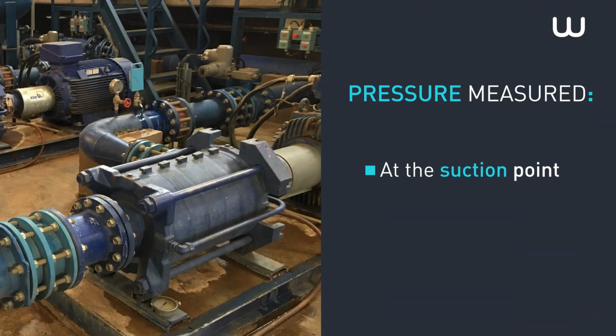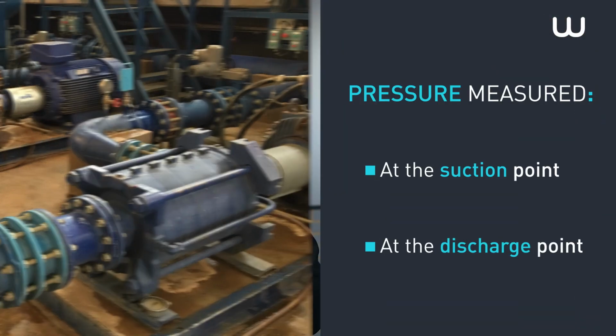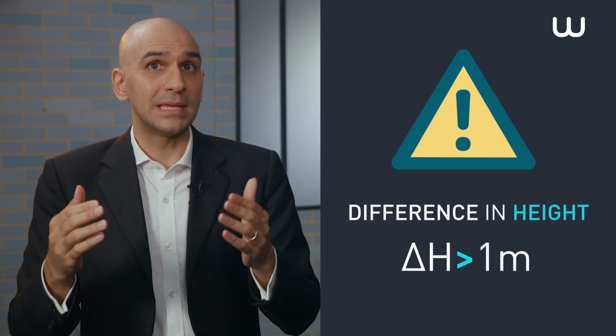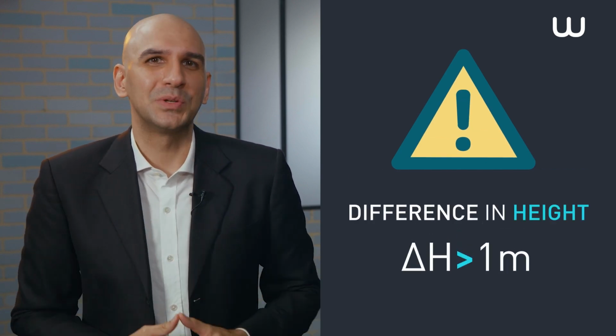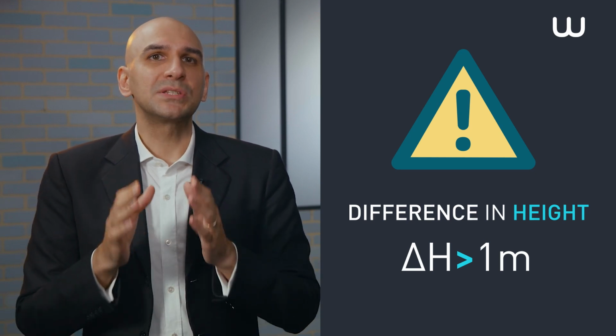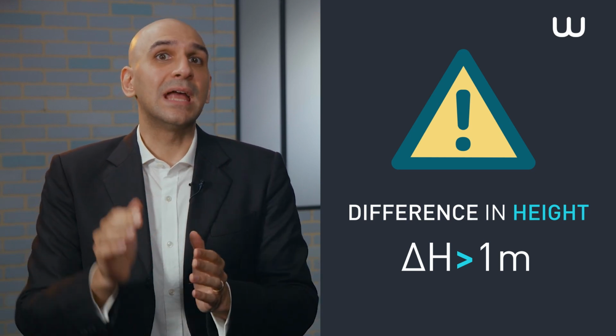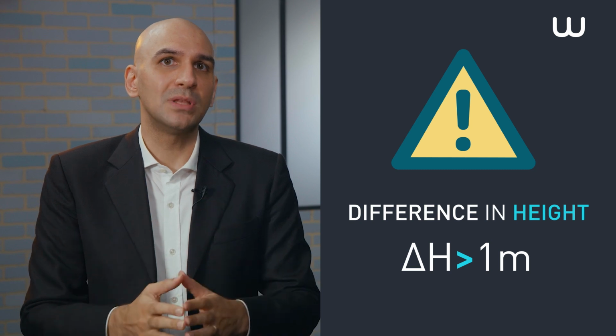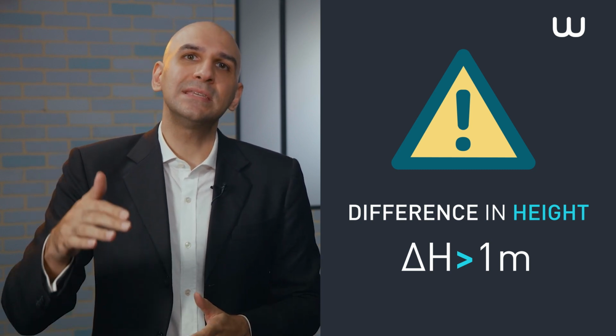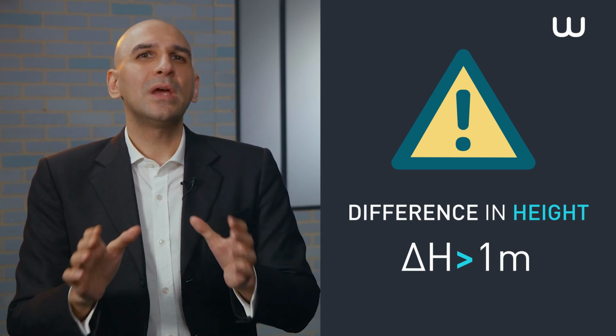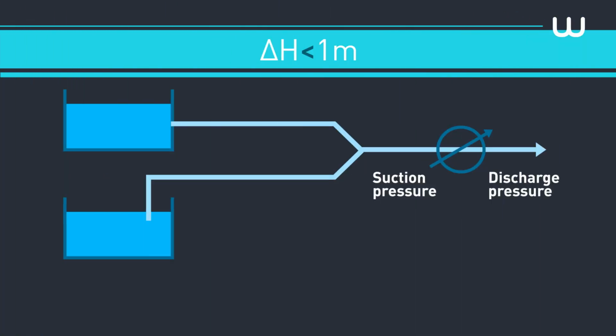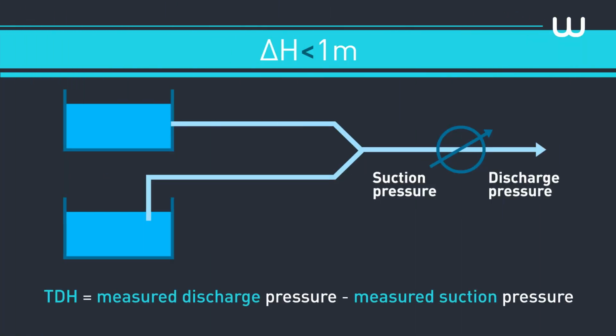In this setup, pressure must be measured at the pump's suction and discharge points, being careful where the measuring points are placed in order to install the manometers. The audit technician must also ensure that the difference in height between these two measuring points is taken into account when it exceeds 1 meter. Where the difference in height is under 1 meter, the TDH is calculated as follows. TDH equals measured discharge pressure minus measured suction pressure.